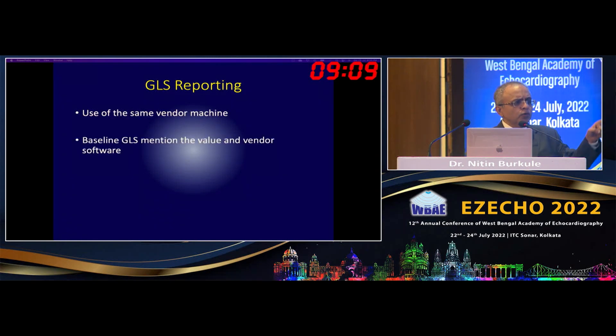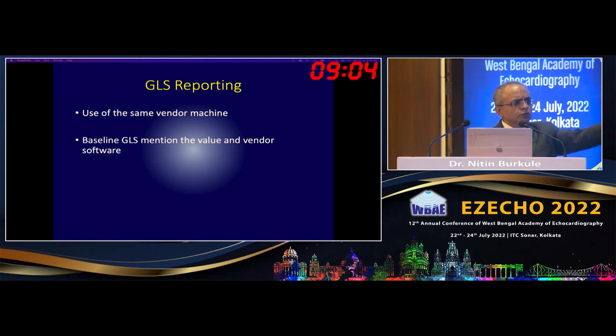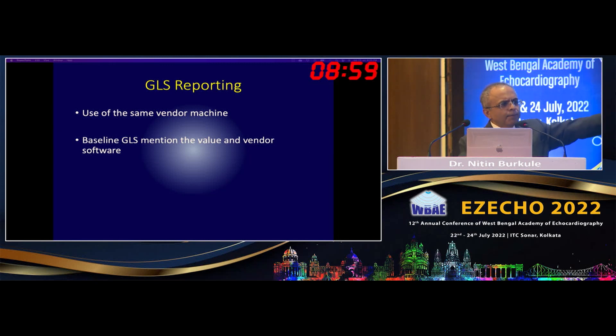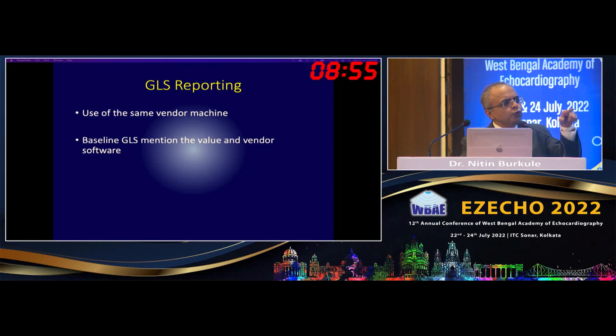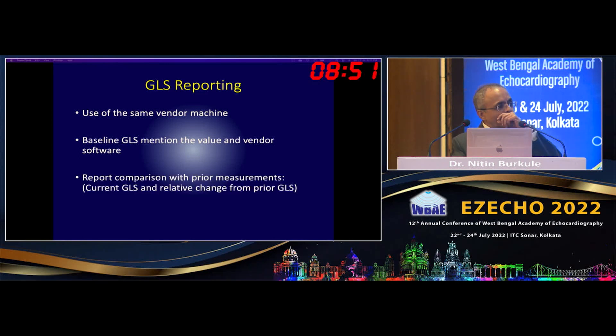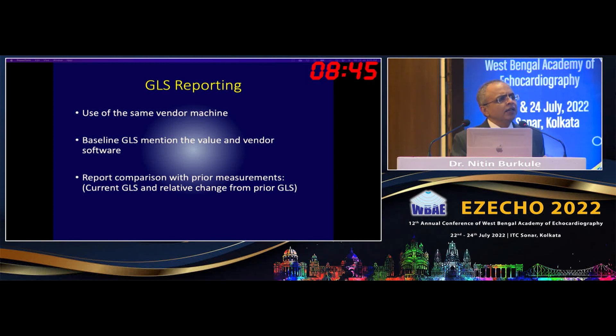When reporting GLS, always use the same vendor machine. Mention on the echo report the specific system, make, and software used — whether done on the system or on TomTec, EchoPAC, or QLab. On the next visit, use the same vendor, same machine, same software. Report the percentage change from baseline, since the oncologist won't know what a normal GLS is.